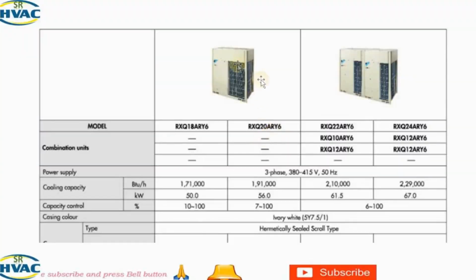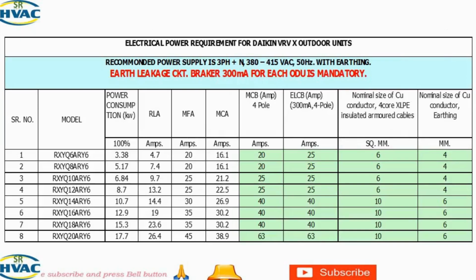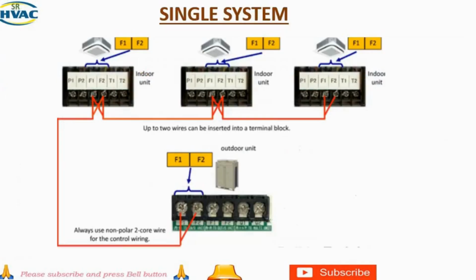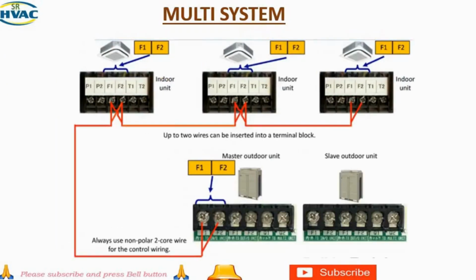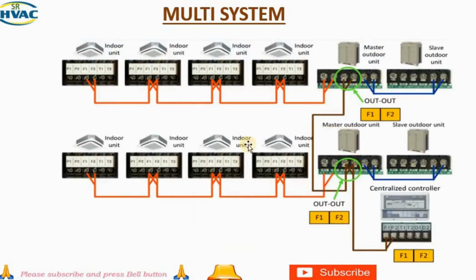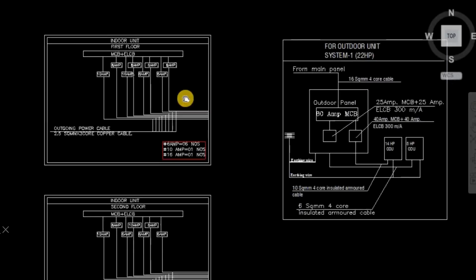by step. In this video, we will cover Daikin VRV top discharge unit, from 6 HP to 20 HP. We will see all the details from power consumption to MCB requirement to the cable to the earthing. We will see the control cable system also for the single system, for the multi system, and for the centralized control system. We will see a project also for the Daikin VRV system.